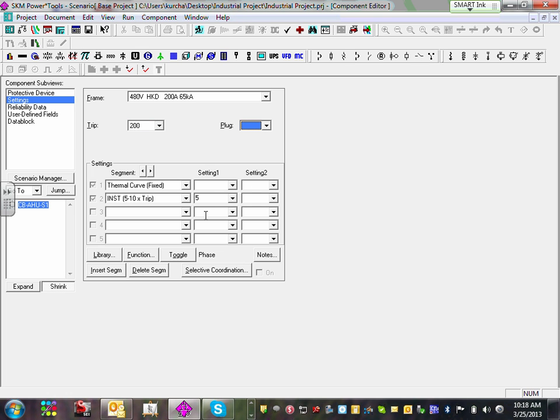I sensor 200 amp and a plug, no plug for this one. It's fixed. And the instantaneous, go all the way and set the instantaneous to the highest, one more time. You're going to set the trip, make sure it's 200, the plug is 200, the trip 200, no plugs, and instantaneous 10.